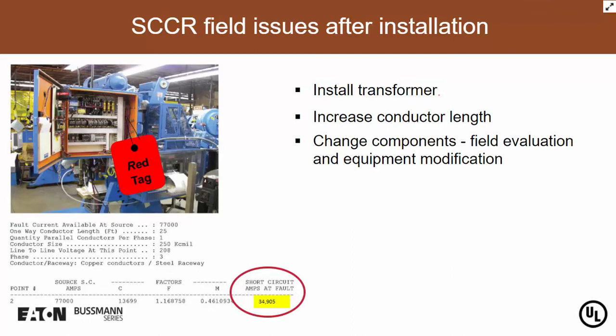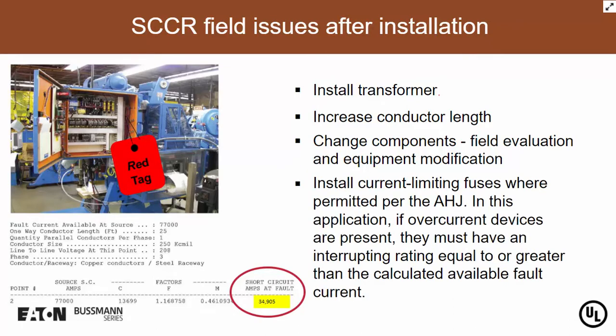And then the other thing we can do is change components. But if we change components, if it's a UL listed panel or a third party listed panel, we would have to get a field evaluation once we change the components. So if we change the components and boost up the SCCR of the components to equal the 35,000 amps that's available, then we may have to get a field evaluation, and we modify the equipment itself. And then finally, what we could possibly look at is installing current limiting fuses in the feeder device, to see if we can use the peak let-through of the fuses to boost up our component SCCR and readjust the SCCR of the machine itself to greater than, let's say, the 35,000 amps that I'm showing.